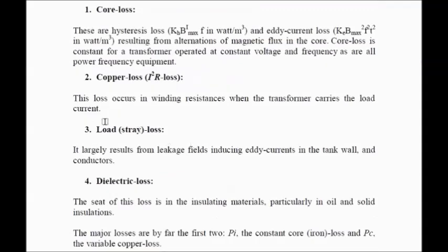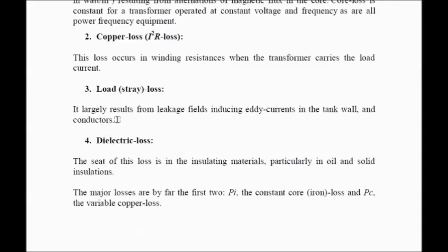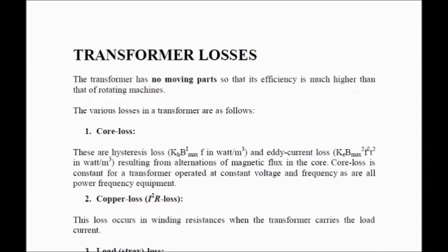Next is load or stray loss, and this is mainly because of leakage field inducing eddy current in tank wall and conductor. So this leakage flux induces eddy current in tank walls also. Because of that eddy current we will have this load loss. Next is dielectric loss, and this is mainly due to loss in the insulating materials, particularly in the oil that we have used and solid insulation. So this is all about transformer losses.